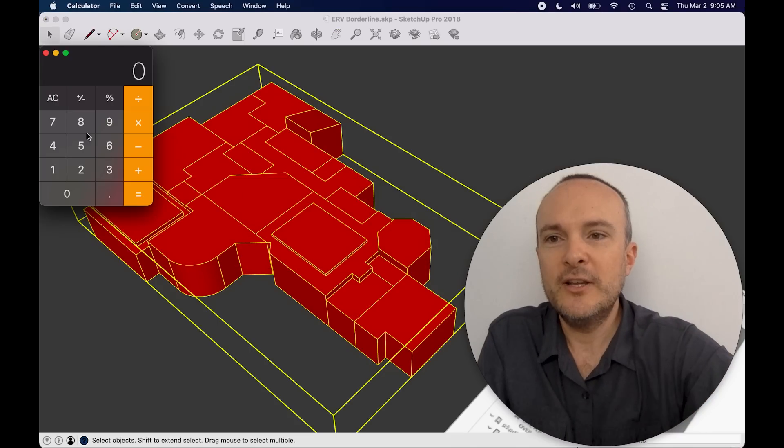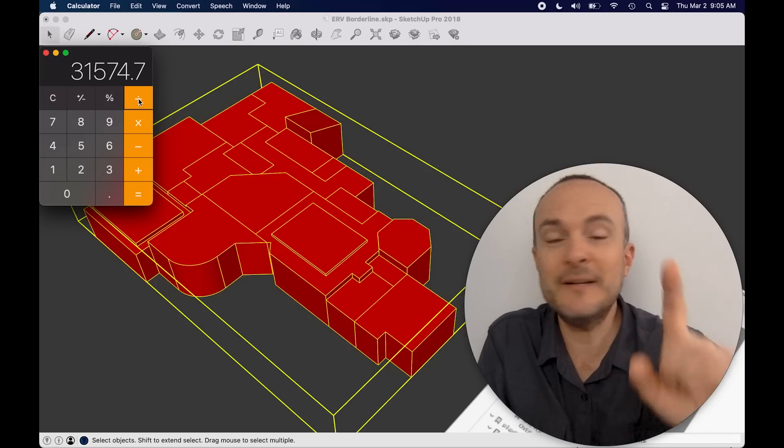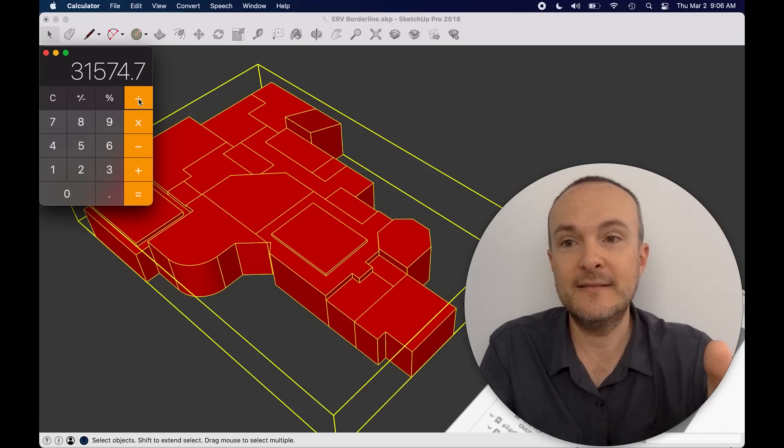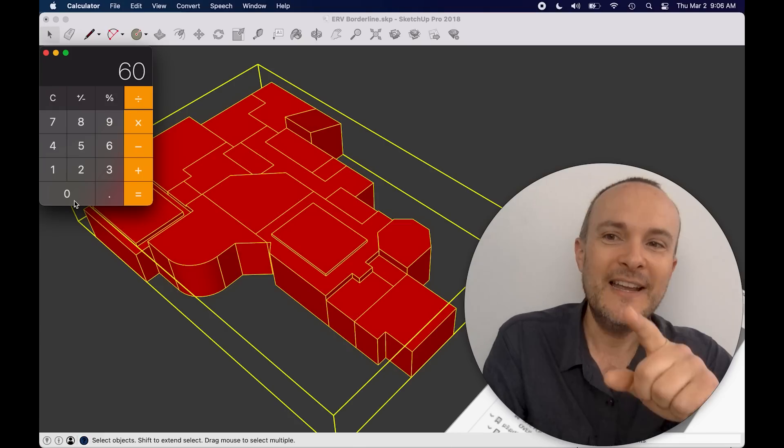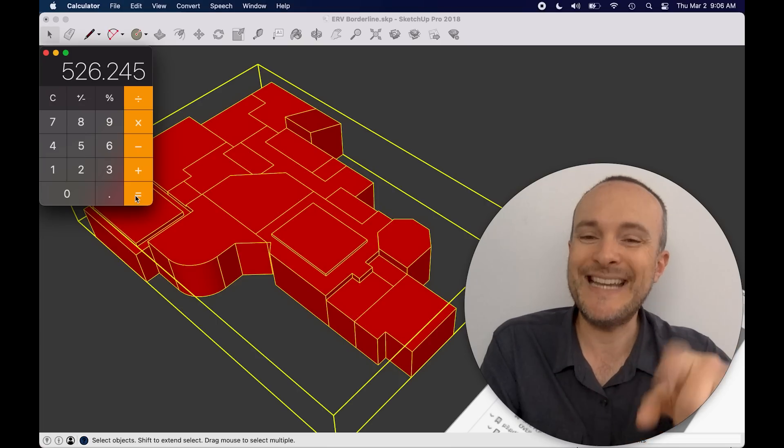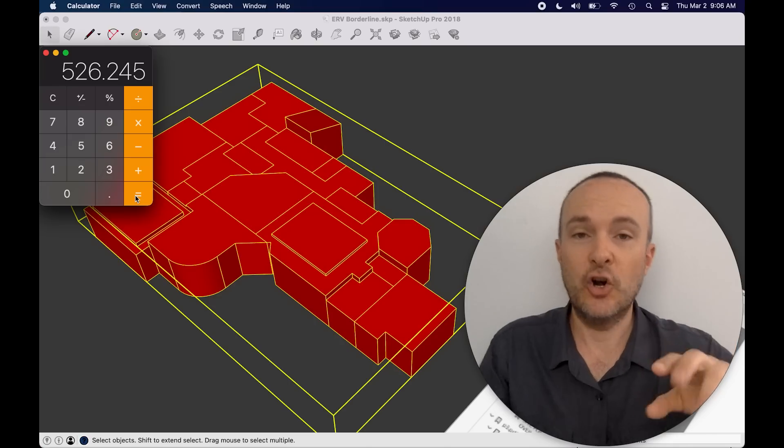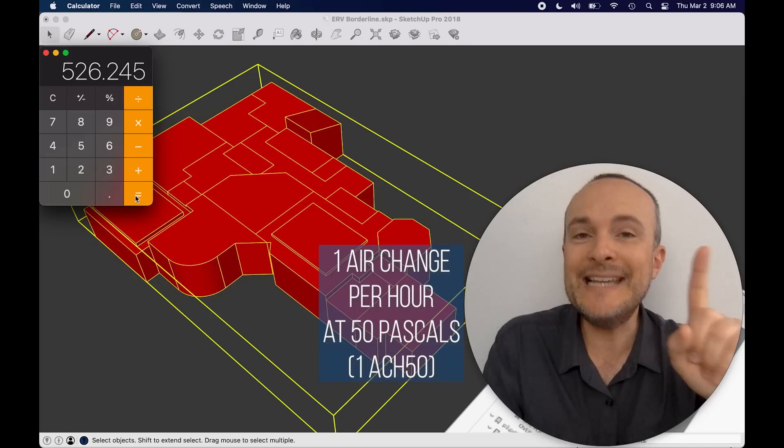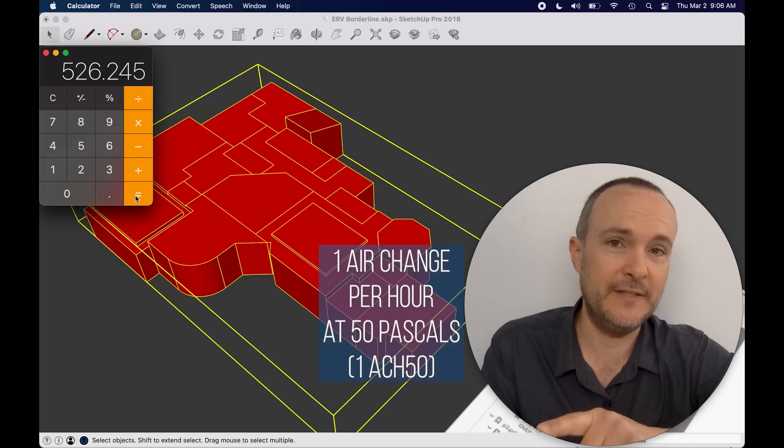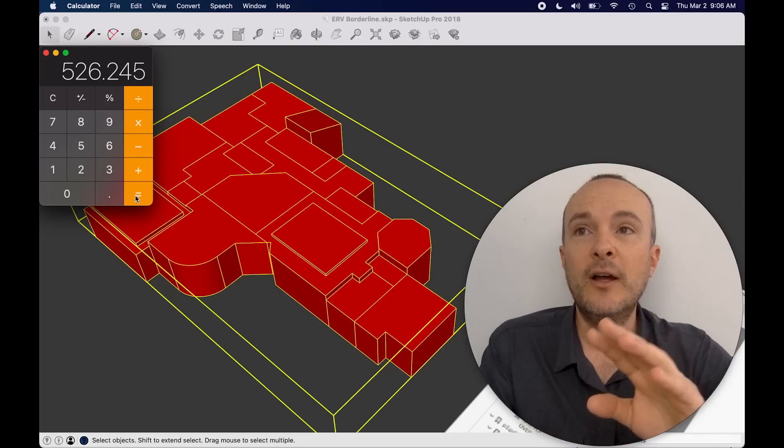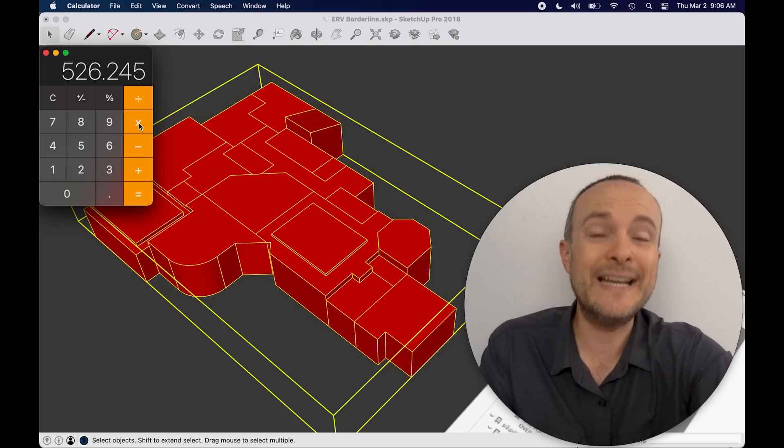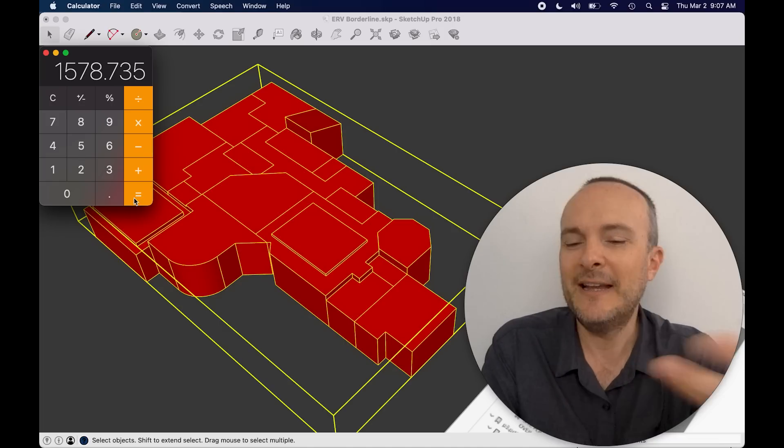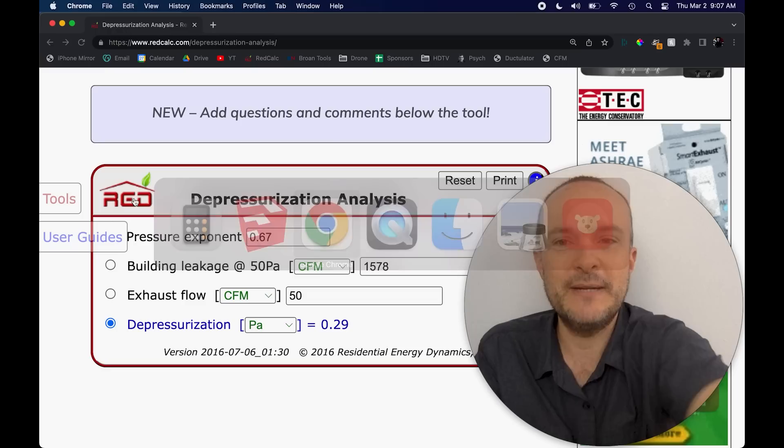So all we have to do now is take the volume 31,574.7, just to be super accurate, because that is the difference between somebody like me and somebody who is more of a schmo is that I will literally be as anal as it takes to be super accurate. And I'll always win those arguments. You divide this number by 60. And that's going to give you your one air change per hour rate during normal operating conditions in this home. But it also for our purposes today is your one ACH 50 blower door number. Now code, the tightest code is ever going to require is three air changes per hour. So all I do is take this number times three, and it gives me 1579 CFM 50.